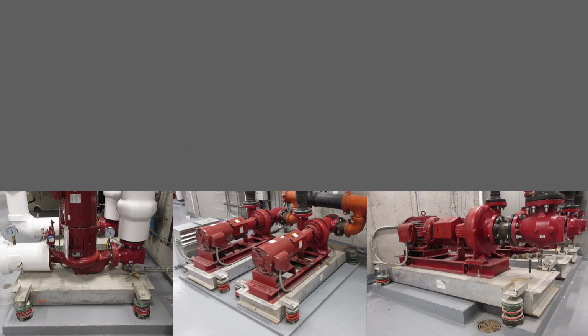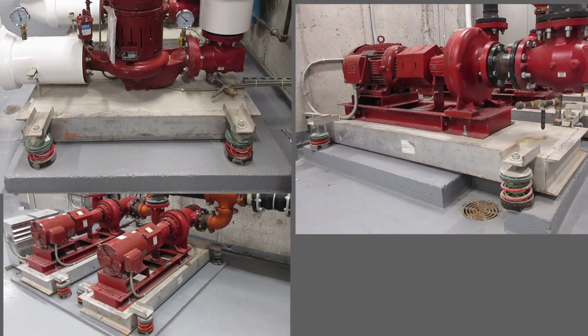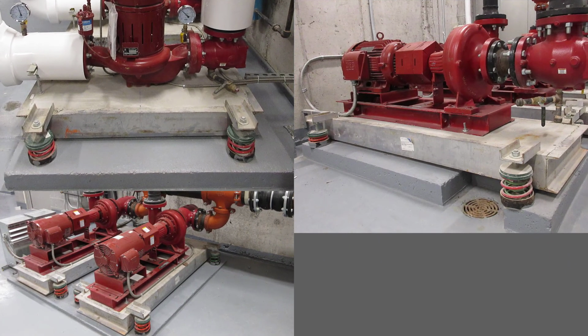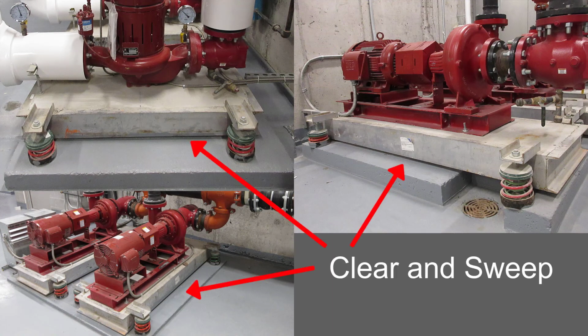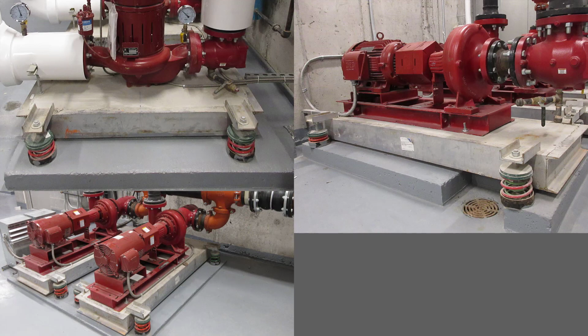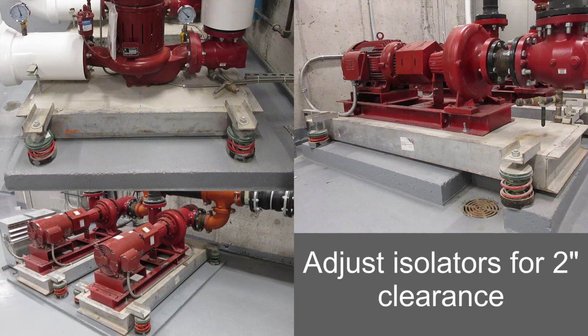So that wraps up our discussion of inertia bases and FS isolators as it relates to this site inspection. Our primary feedback to the contractor on this one is to sweep out under the inertia bases and make sure there is no debris that could be causing a vibration isolation short circuit. If they need an installation certification, they will need to raise the bases to have clearances closer to 2 inches.